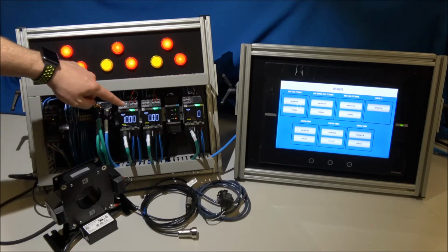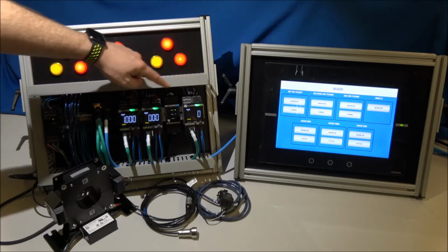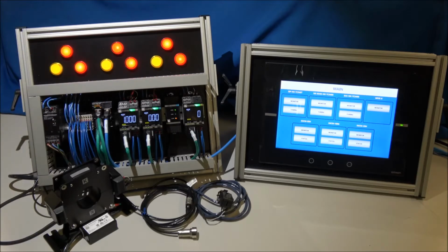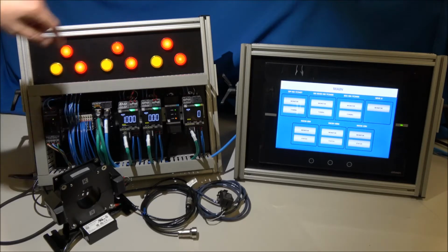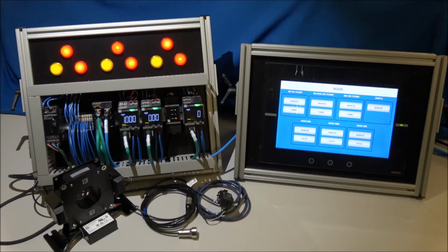As you see here on the local display, we're showing green on each one. This local display will show green, yellow, or red, depending on if the thresholds are hit. Up at the top here, you can see these LEDs are connected to each of the transistor outputs.